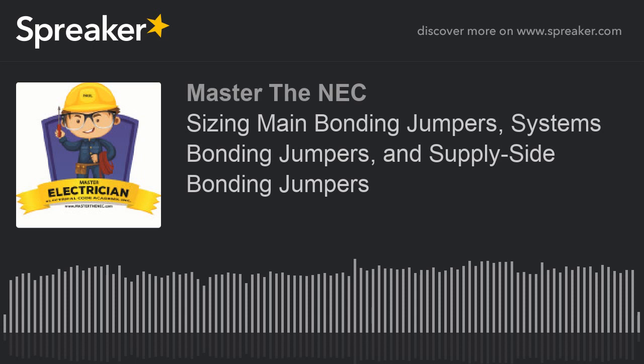Okay, so let's get back to what we're talking about. So the material, what can be a grounded conductor, bonding conductor, and jumper? It says material, 250.102A, bonding jumpers shall be of copper, aluminum, copper-clad aluminum, or other corrosion-resistant material. So here's a neat thing. Remember when I was talking earlier, it said the main bonding jumper has to be copper or other corrosion-resistant material? But it didn't say the same thing as 250.102A. We probably should change that because if you read here, it clearly states that copper, aluminum, and copper-clad aluminum are corrosion-resistant material. It's not that they don't corrode.